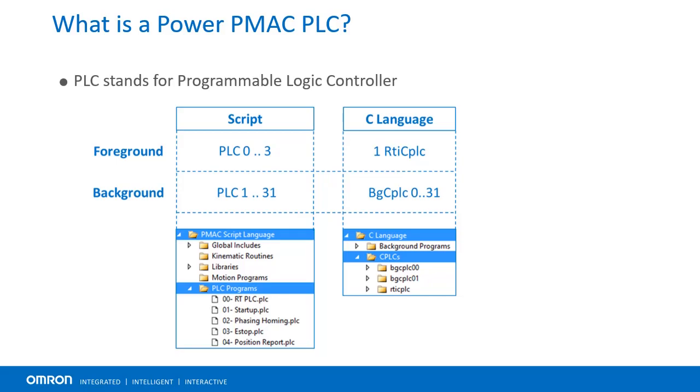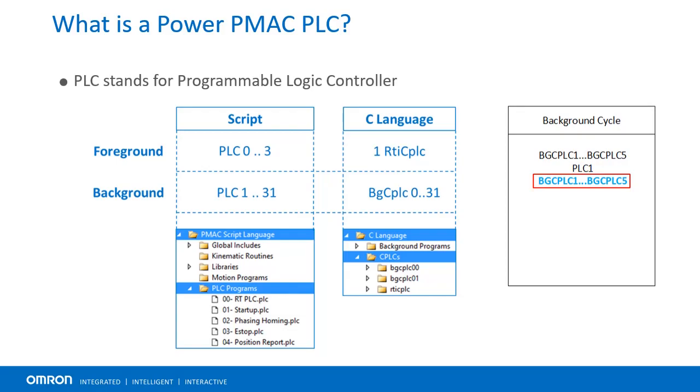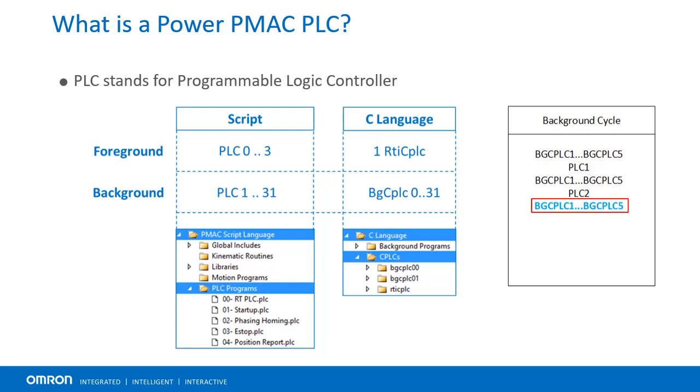Both foreground and background PLC programs have dedicated numbers and can be composed in either PMAC's own script language or C environment in the IDE software. Note that during a background cycle, PMAC scans all C PLCs simultaneously, then scans the first script PLC, scans all the C PLCs again, then the next script PLC, and so on.